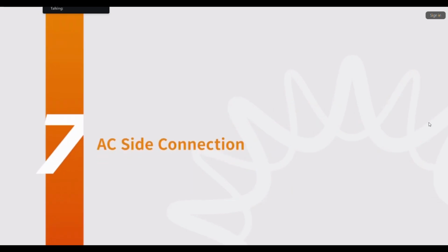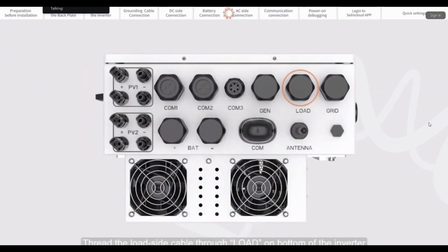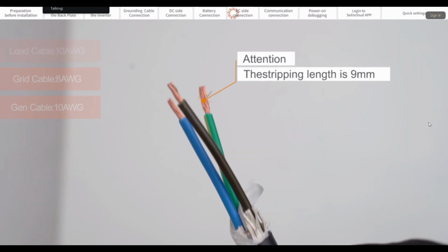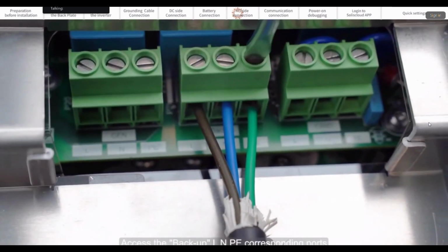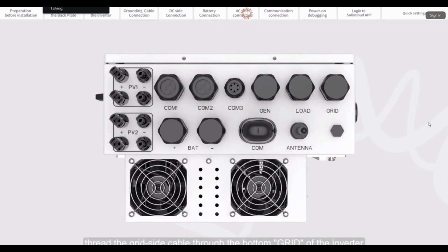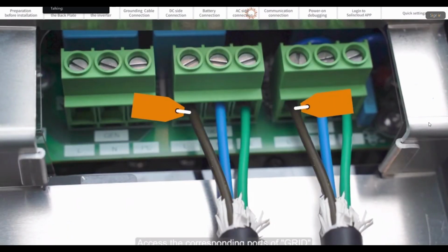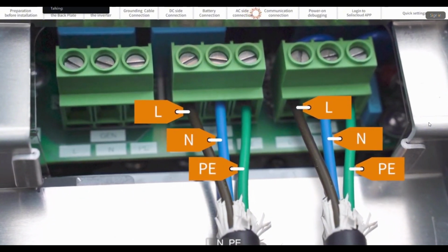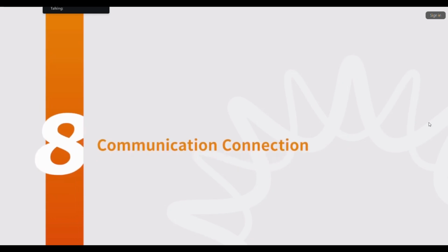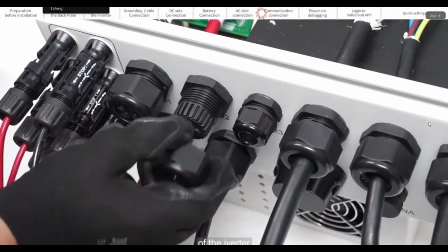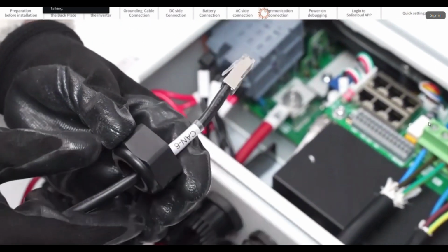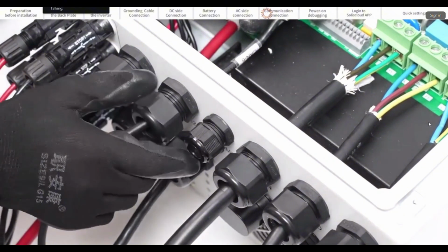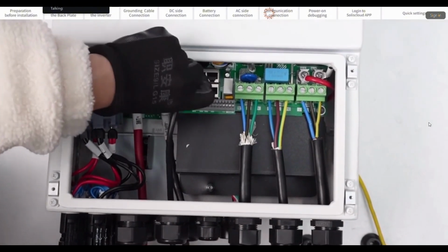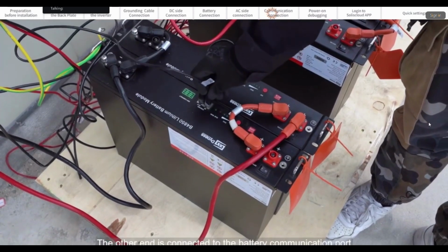Part 7. AC side connection. Pass the load side cable through the load at the bottom of the inverter. Access the backup line, neutral, earth corresponding ports. Similarly, pass the grid side cable through the bottom grid of the inverter and access the corresponding ports of the grid, line, neutral, and earth. Part 8. Communication connections. Thread the communication cable through the COM on the bottom of the inverter. One end is connected to the BMS port, and the other end is connected to the battery communication port.